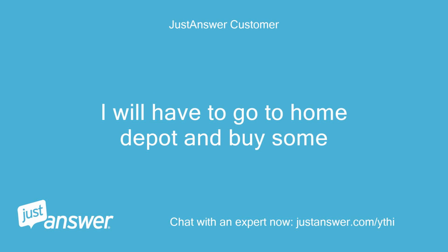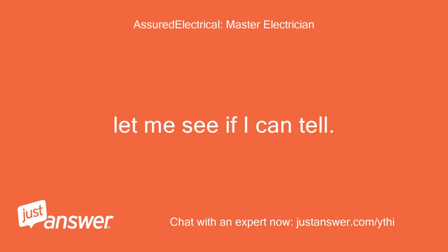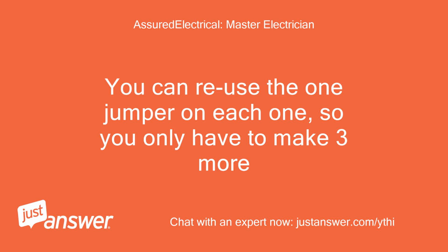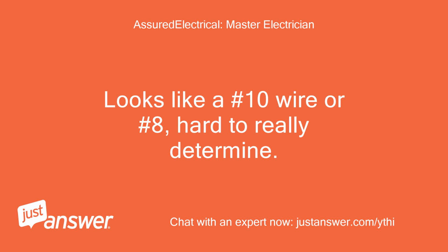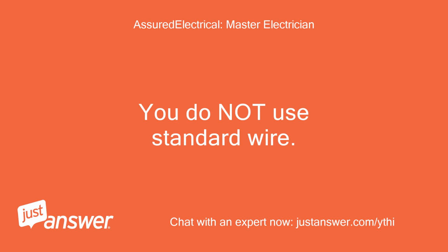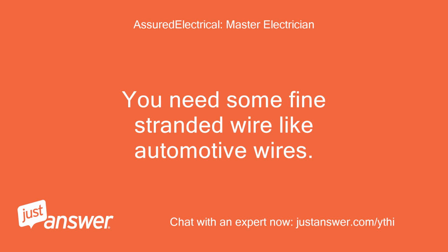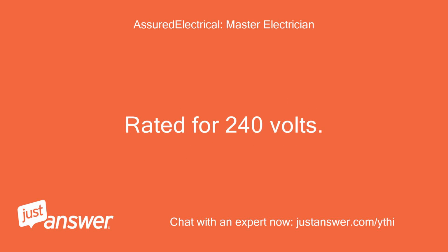I will have to go to Home Depot and buy some. Let me see if I can tell. You can reuse the one jumper on each one, so you only have to make 3 more. Looks like a number 10 wire or number 8, hard to really determine. You do not use standard wire. You need some fine stranded wire like automotive wires. Rated for 240 volts.